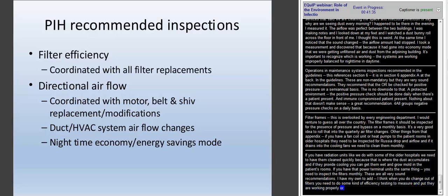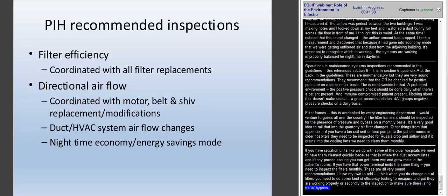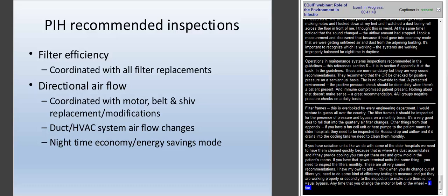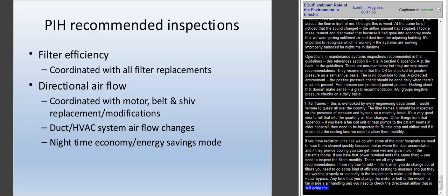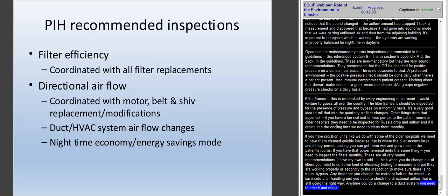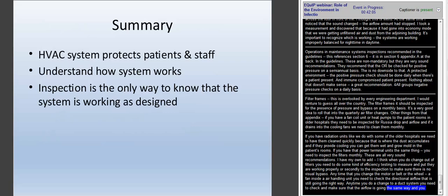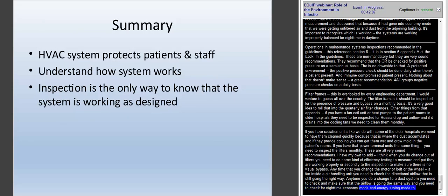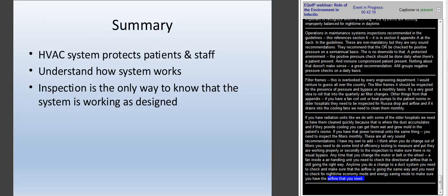And any time that you change a motor or a belt or the wheel, what's called a sheave, on a fan inside an air handling unit, you need to check that the directional airflow in the rooms is still going the right way. Anytime you do a change to a duct system or an HVAC system, you need to check to make sure the airflow is still going the same way. And you do need to check for nighttime economy mode and energy saving mode to make sure you've got the directional airflow that you need. So to summarize, HVAC system basically protects patients and staff from what's outside.